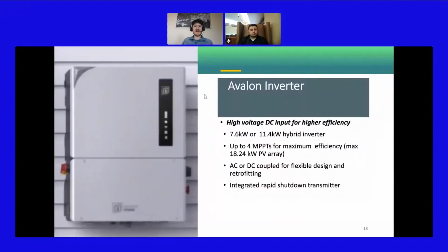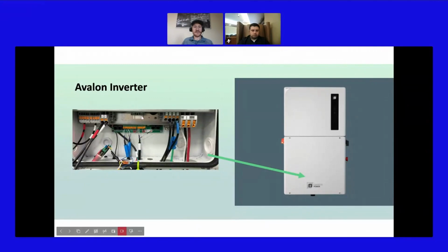Now the next component is the Avalon inverter. This comes in a 7.6 or an 11.4 hybrid inverter, and it includes up to 4 MPPTs, and you can do up to an 18.24 kilowatt DC PV array on each 11.4. It can be AC or DC coupled, and it has an integrated rapid shutdown transmitter in the inverter. The rapid shutdown transmitter is right up here if we had a bigger picture. Basically the battery ties into the Avalon inverter as well as your 4 MPPTs from the solar array.